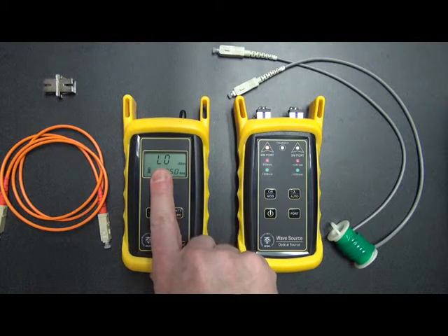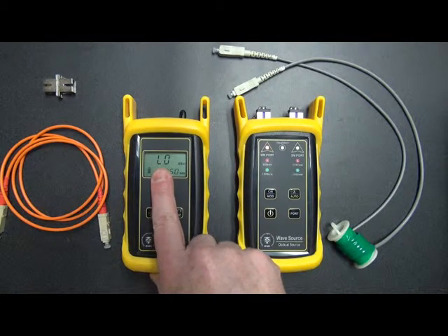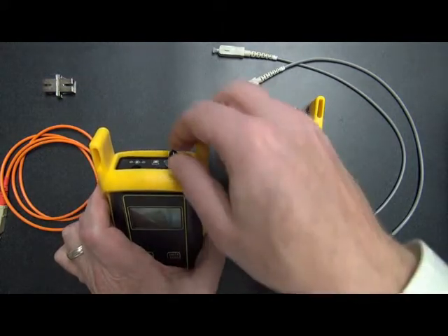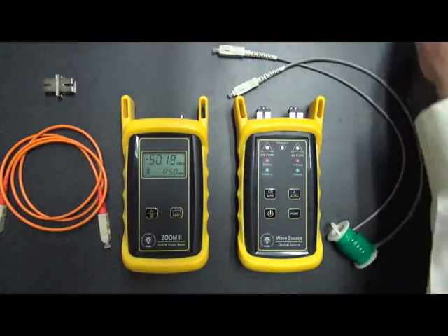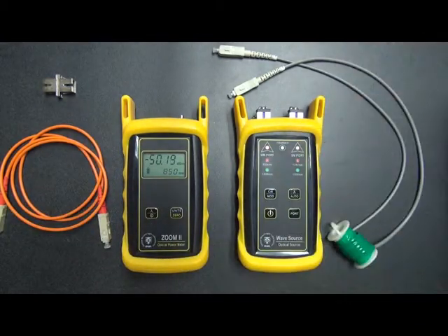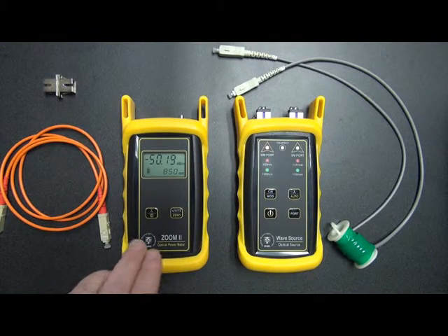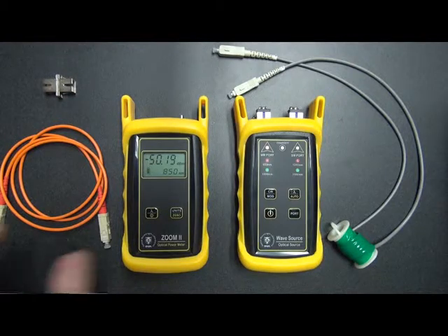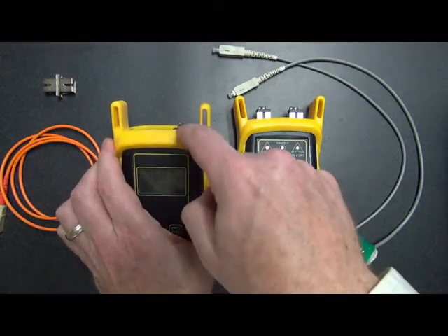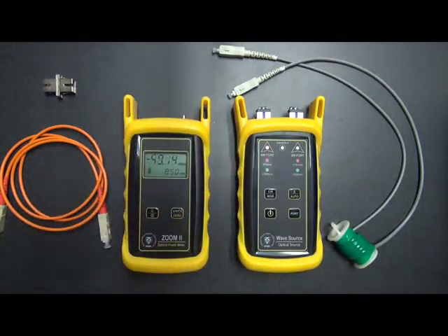What this means is that there's no measurable amount of light coming into the photodetector. This is because there's a dust cap on the detector. If we remove this dust cap, we'll notice that we get a power reading. However, this is a very low power reading simply because we are measuring ambient room light. So just keep that in mind when you see a reading like this. It could be ambient room light, especially if there's nothing connected into the detector port.